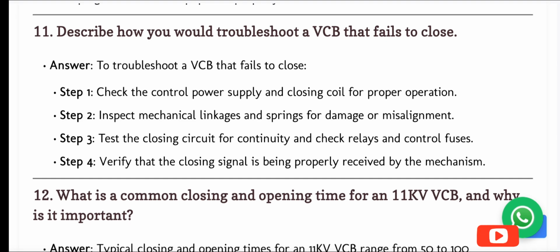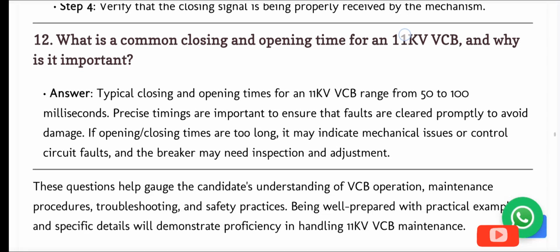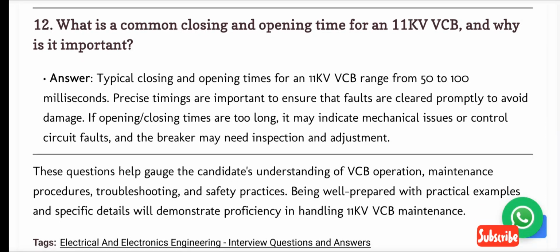12. What is a common closing and opening time for an 11 kV VCB, and why is it important? Answer. Typical closing and opening times for an 11 kV VCB range from 50 to 100 milliseconds. Precise timings are important to ensure that faults are cleared promptly to avoid damage.